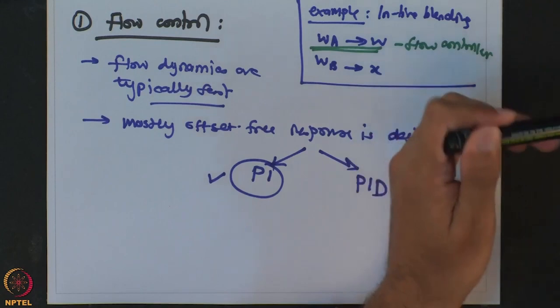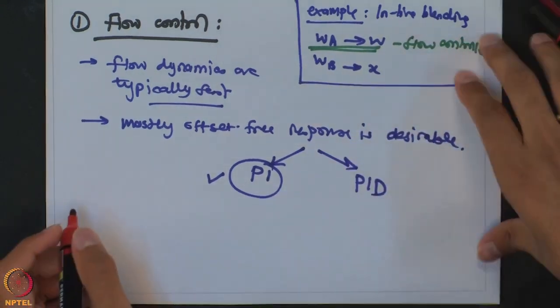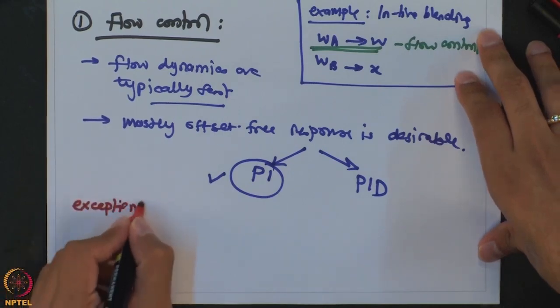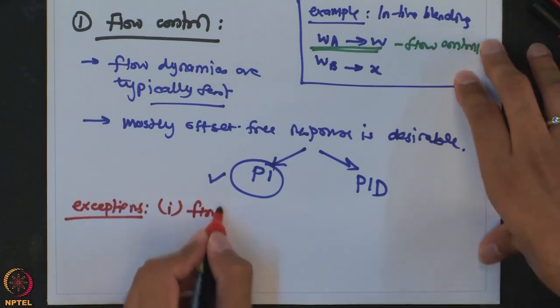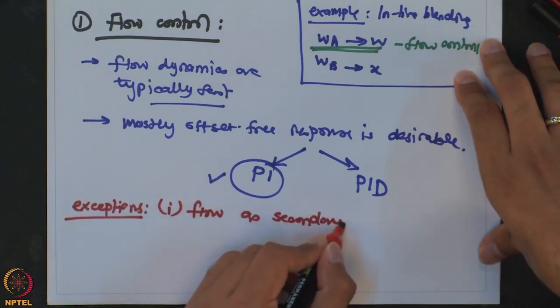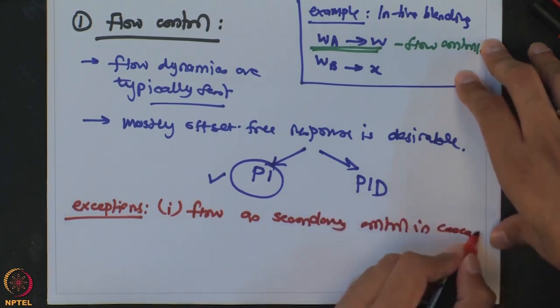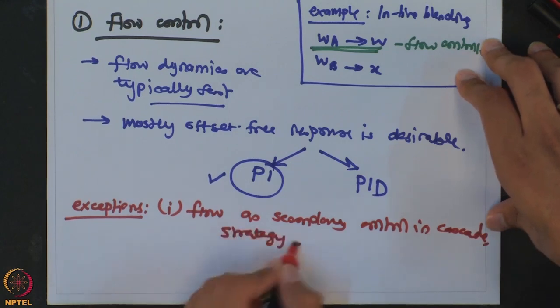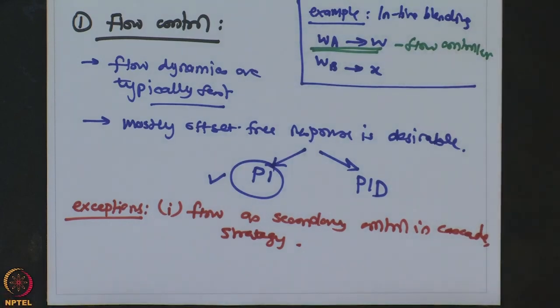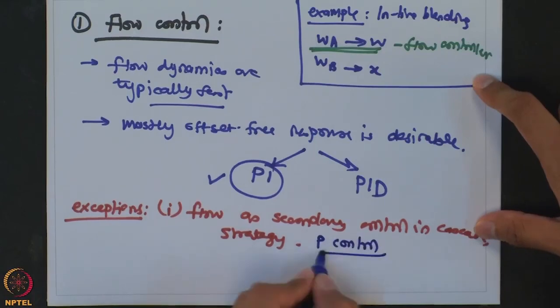Now there are two exceptions to this rule. The first is flow as a secondary control objective in a cascade strategy. We have not yet seen what cascade control is, but it is a control strategy where two control loops are connected together — one is a primary control loop and the other is a secondary control loop. When flow is part of this secondary control loop, offset is not that critical and is tolerable. So in such a case, in order to improve the speed of response, you may have flow as a proportional controller.